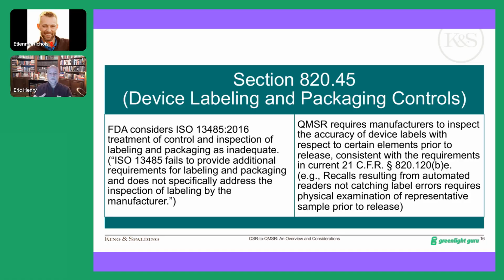where they have had recalls from medical device manufacturers who had an automated device that read the labels and supposedly marked out, pulled, or did not allow to be applied labels that were somehow incorrect. But those automated systems are still prone to error, and some of those errors have driven recalls. So the FDA says, fine if you're using those systems, but we still expect you to take a statistically significant sample of those labels, even if they are inspected using an automated tool, and review them with a human prior to release of the product. And so the FDA comes down much harder on the inspection of labels in this section than the standard does, and they actually feel that's a deficiency in the standard that they want to compensate for in the regulation.